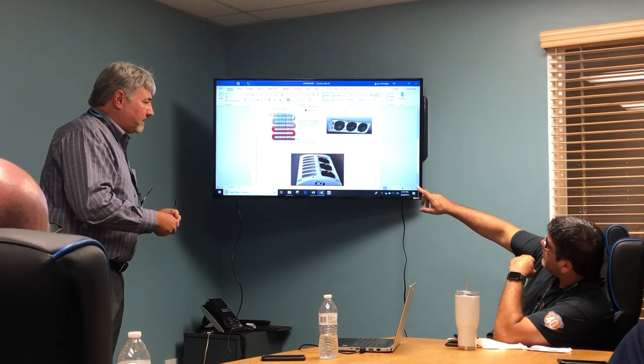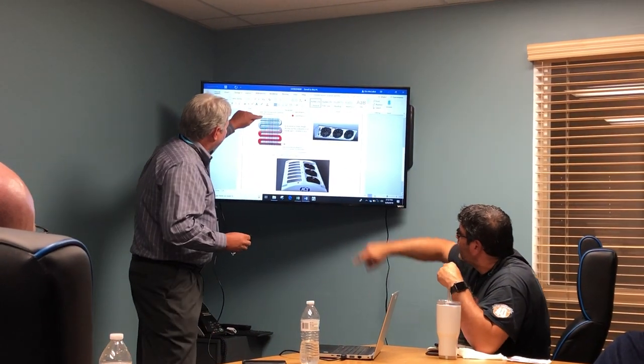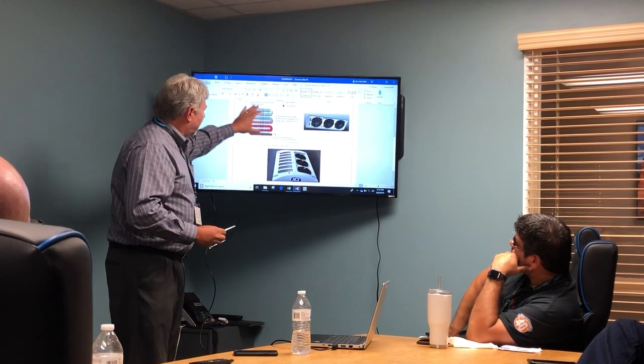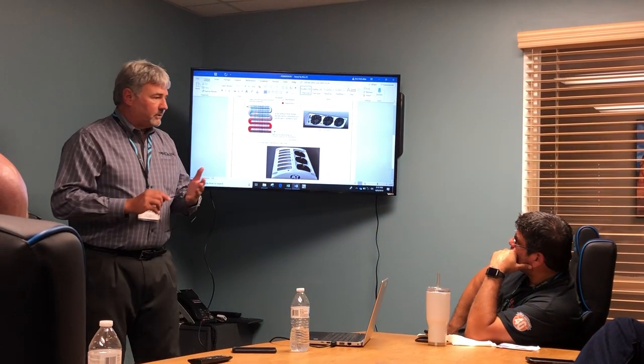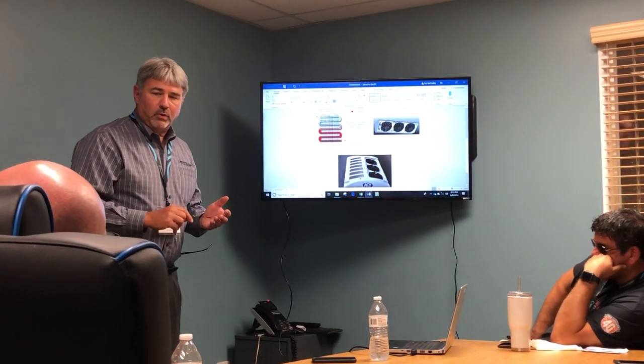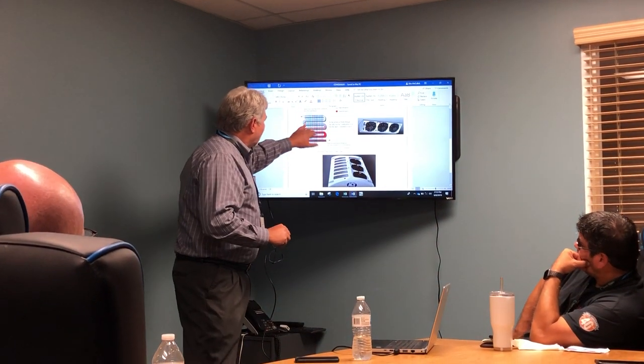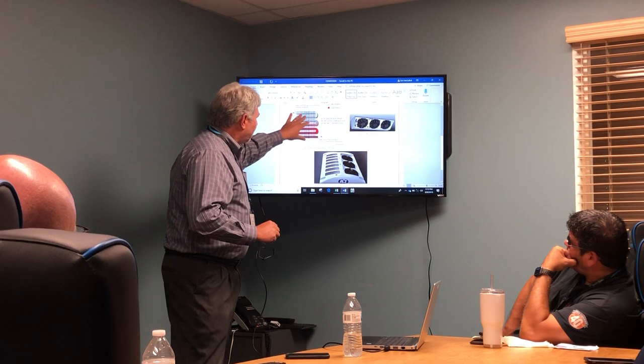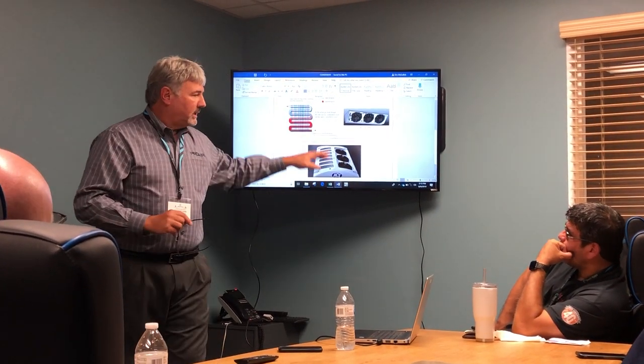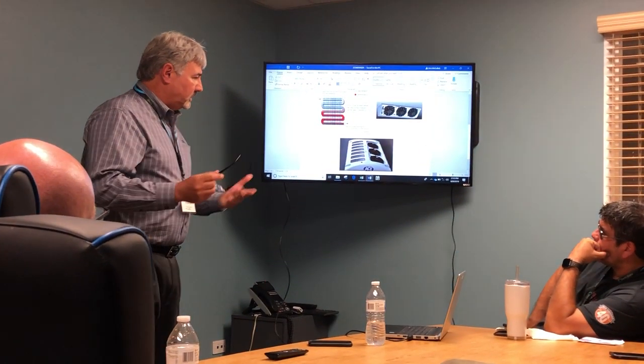So if it's not working properly, a lot of times they say you need to clean it out. And are they talking about cleaning this part out? They're talking about cleaning the coils out, making sure they're getting clean. And one enemy of a skirt condenser is the sodium chloride and the salt brine that they use on the roads. That unfortunately doesn't work well with aluminum, and that's usually what most of these are. We actually use a copper and an aluminum in the Pro Air systems, but just keeping them clean, especially keeping them washed out, making sure the fans are in good shape, your system's going to live longer.